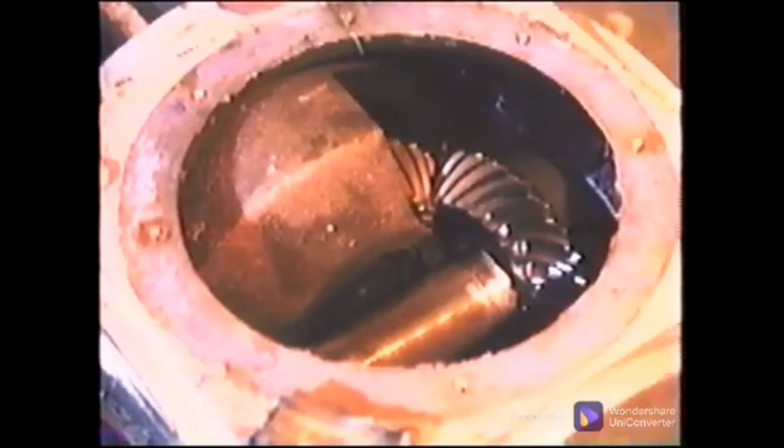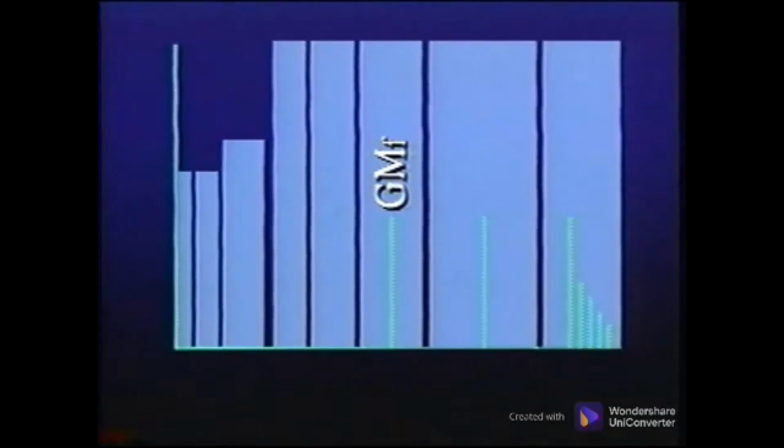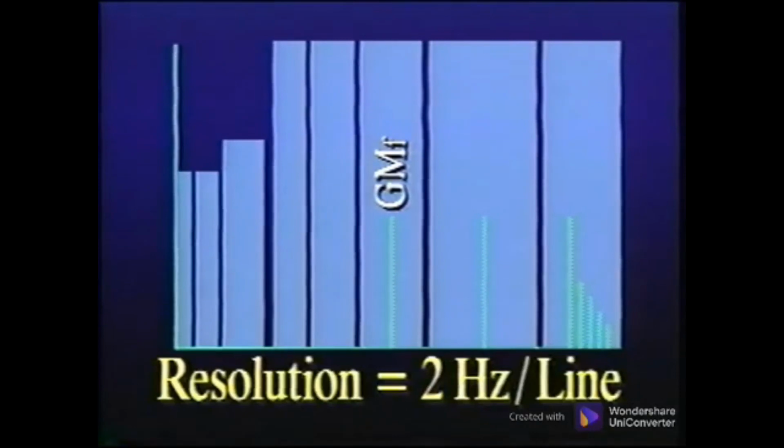For low speed and speed reduction gearboxes, where the gear mesh frequency is less than 600 Hz, the same parameters can be set. For programs that have the ability to specify more than six parameters, the lower frequencies can be defined as a typical bearing measurement point, and simply add the bands for the gear mesh frequencies. Make sure the resolution is about 2 hertz per line, and this measurement point definition can save you the need to make 2 measurements at each sensor location.